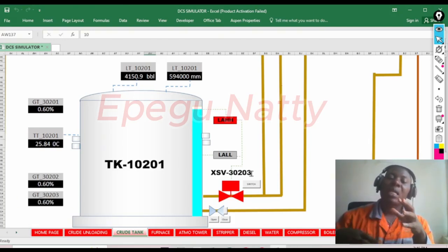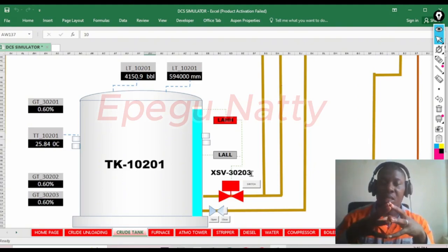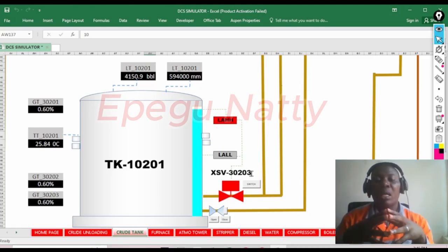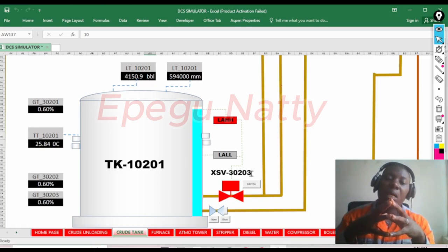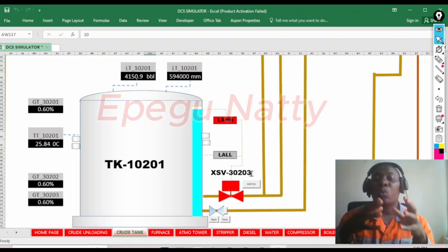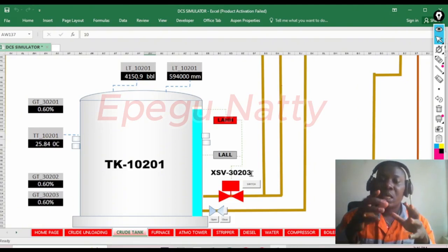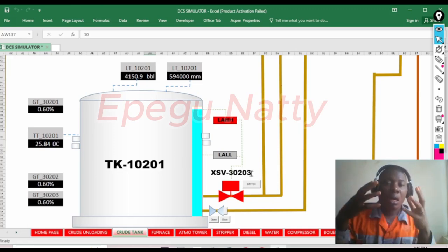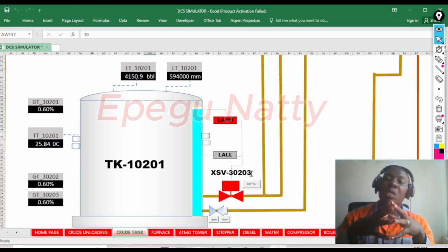Now, but what if we accredit a different device? What if we accredit the fire or the gas detector? What if I accredit the gas detector to be part of this system? Then this is not a SIS. This is going to be a BPCS, just a basic process control system. All right. So we need to understand this.